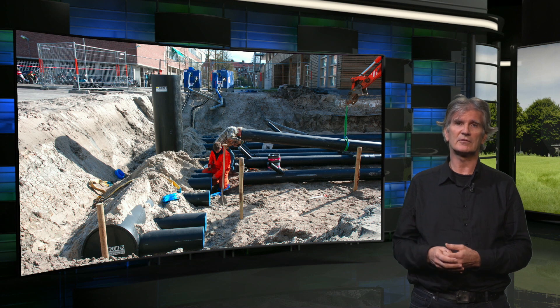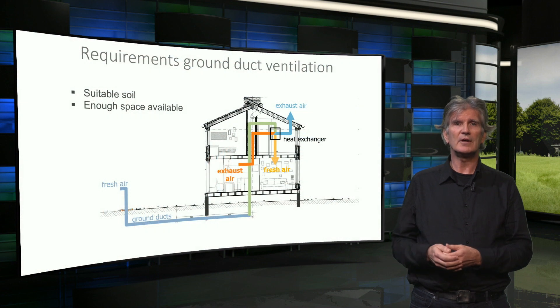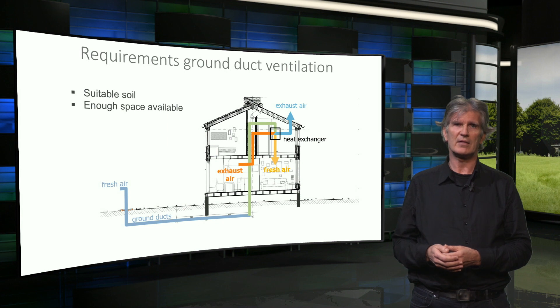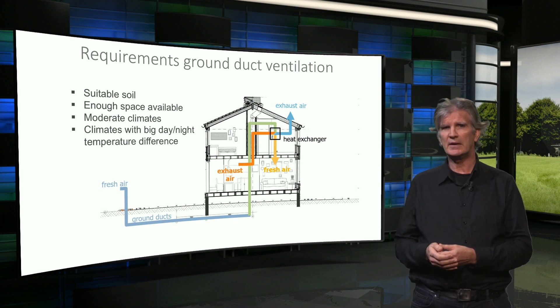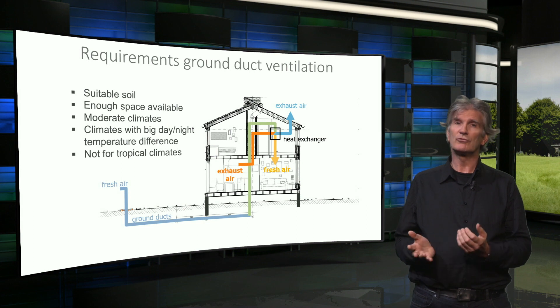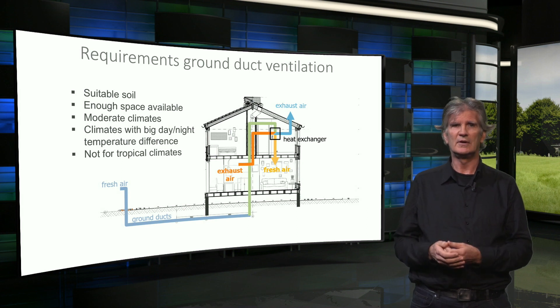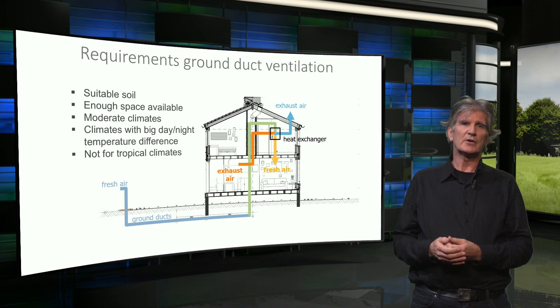It is obvious that this ground duct technology is not feasible everywhere. First, the underground must be suitable to bury the ducts, and there must be enough space to provide enough length for the ducts. Furthermore, the climate must be suitable. In a moderate climate with cold winters and warm summers, it is most effective. It also works in climates with a big temperature difference between day and night. But in a tropical climate with a high average outdoor temperature, it is not effective, because the temperature difference between the air and the soil is too small.